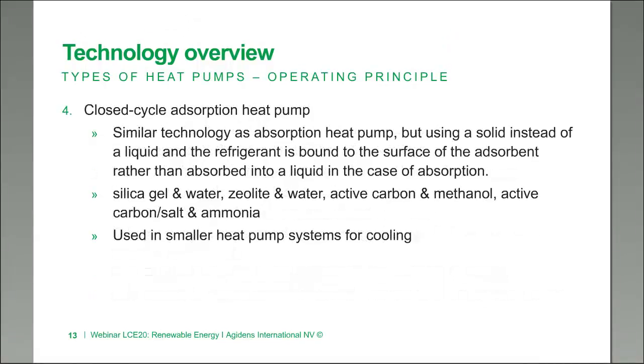The final closed cycle heat pump type is the adsorption heat pump, very similar to the absorption heat pump but the difference is that with adsorption you use a solid instead of a liquid — the refrigerant is bound to the surface of the adsorbent rather than absorbed into a liquid. Some examples are silica gel and water, zeolite and water, active carbon and methanol, and active carbon and salt with ammonia. These tend to be used in smaller heat pump systems for cooling and are not commonly seen for heating purposes in industrial applications.